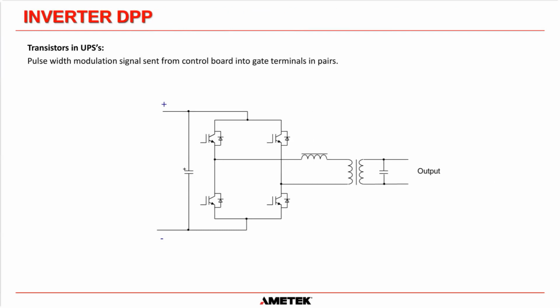And what that allows us to do is regulate the output of the system very, very tightly. If there was a current demand or we needed to change the voltage of the output of the inverter for any reason, all we have to do is change those pulses in real time, and we can regulate the output of that system without a ferroresonant transformer and have extremely tight regulation going out of our inverter bridge.